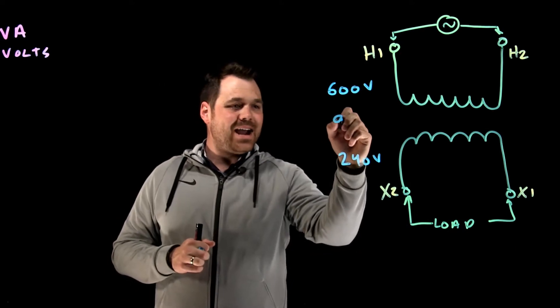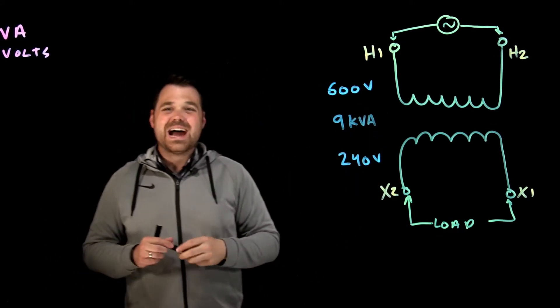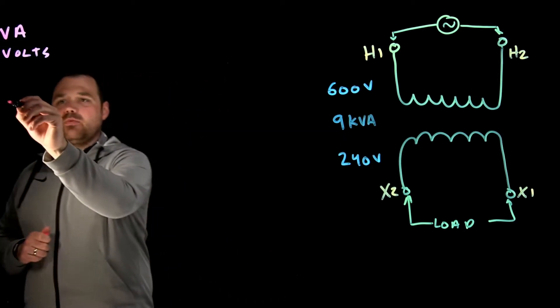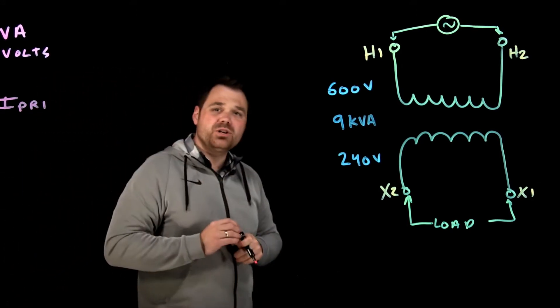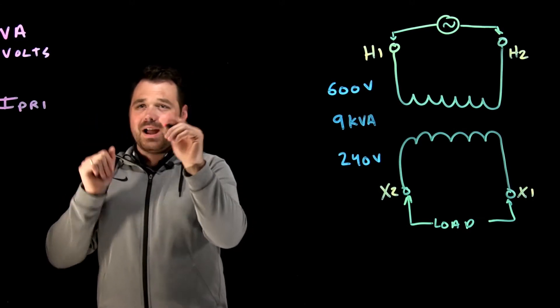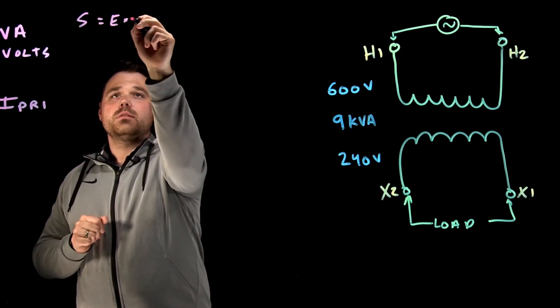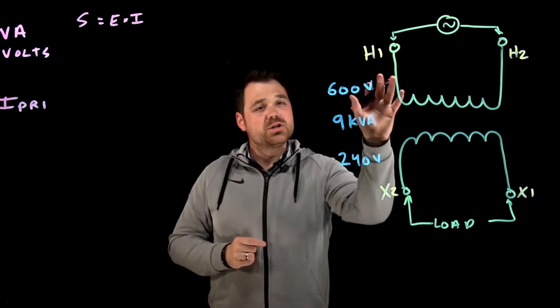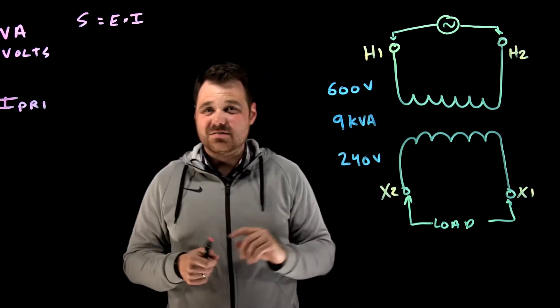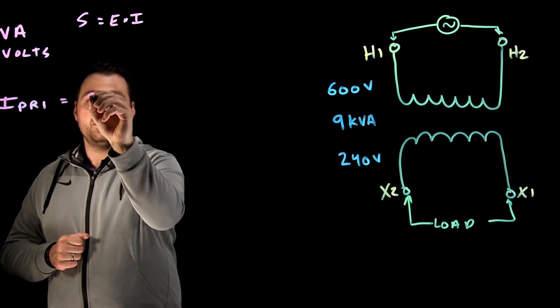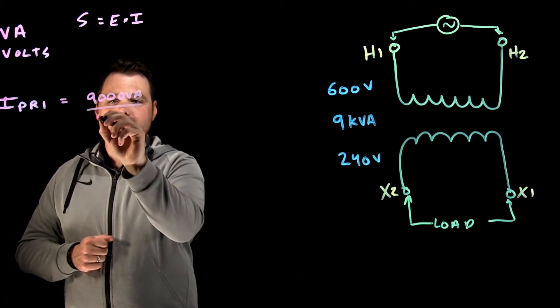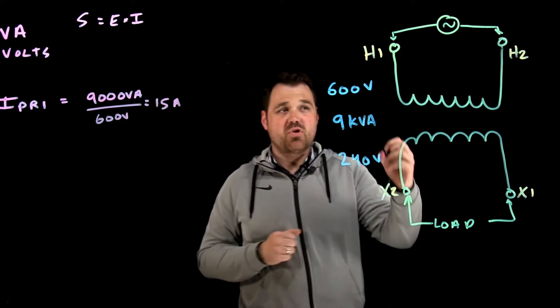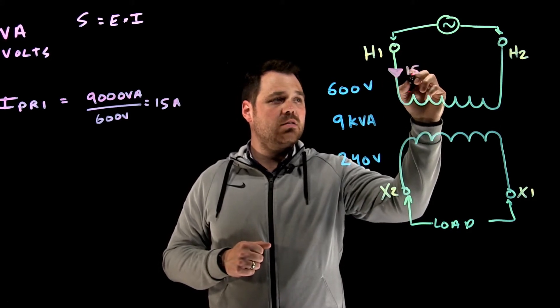For this transformer, let's say it is a 9 kVA transformer or 9,000 volt amps. I want to calculate current. Let's start with the primary. I'm going to take my apparent power formula. We know that S equals E times I. I'm going to transpose it. So I'm going to take my apparent power divided by my voltage. On my primary side, I've got 600 volts and 9,000 VA. So 9,000 VA divided by 600 volts gives me 15 amps. My primary current is 15 amps.